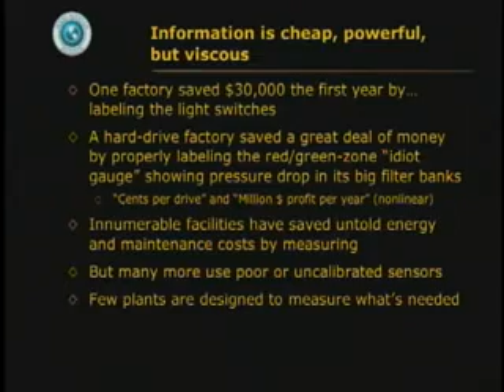Of course, many measurements aren't worth anything because they're done with poor or uncalibrated or drifted sensors, and very few plants are designed to measure what's needed. I'm only aware of two chip fabs in the world where there's a long enough clear run of main chilled water pipe to get an accurate measurement off a flow meter. That means there was never an original design intent to measure the flow accurately and therefore to figure out how much energy it's taking to make a unit of chilled water, because there was no intention to improve the design.